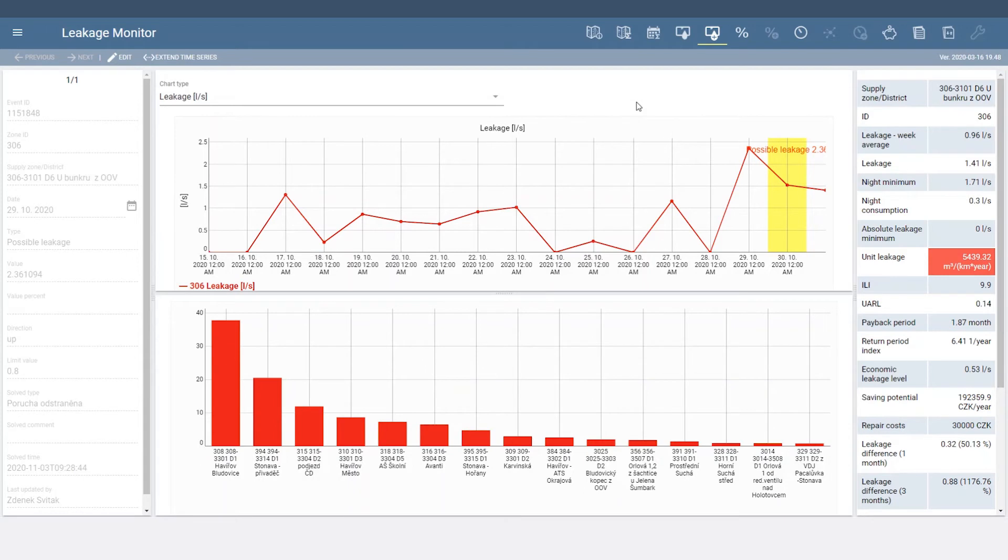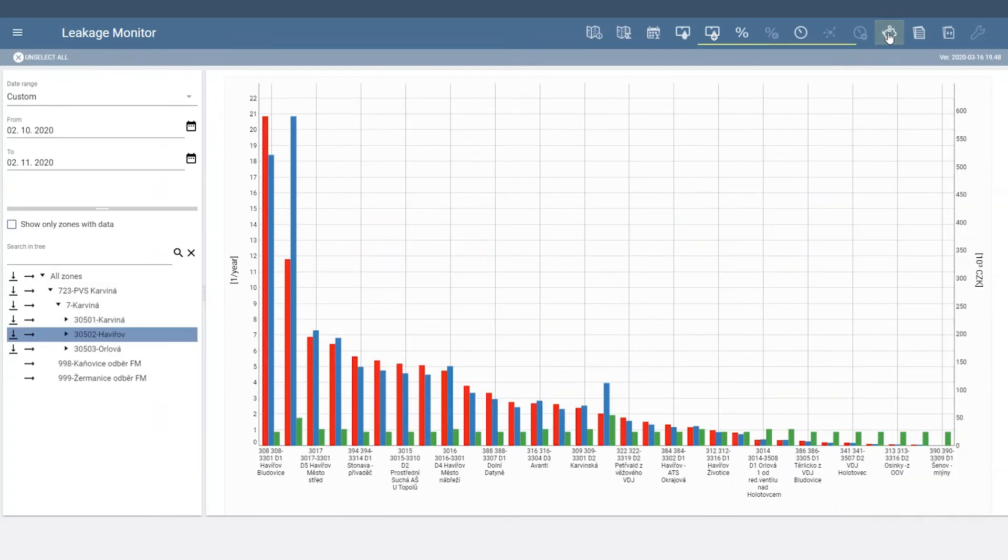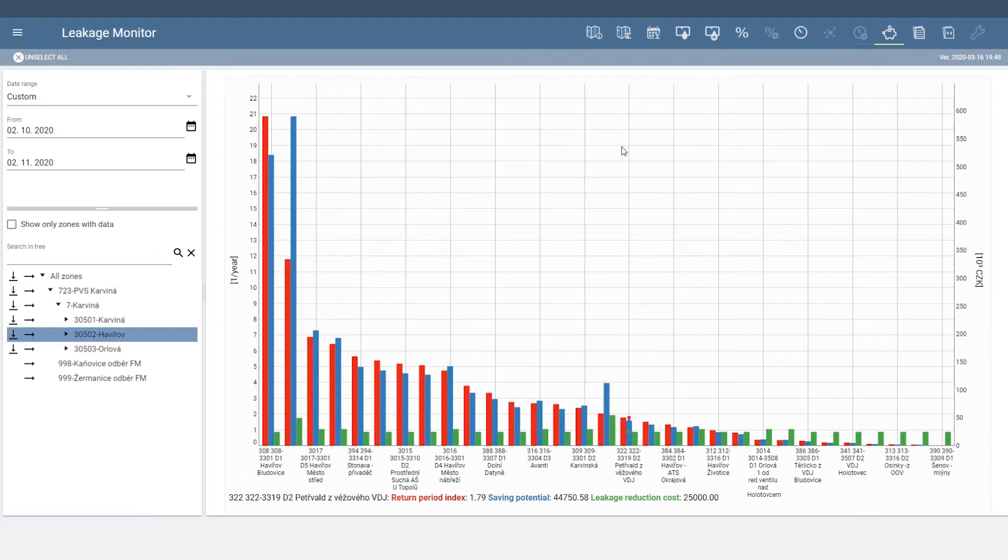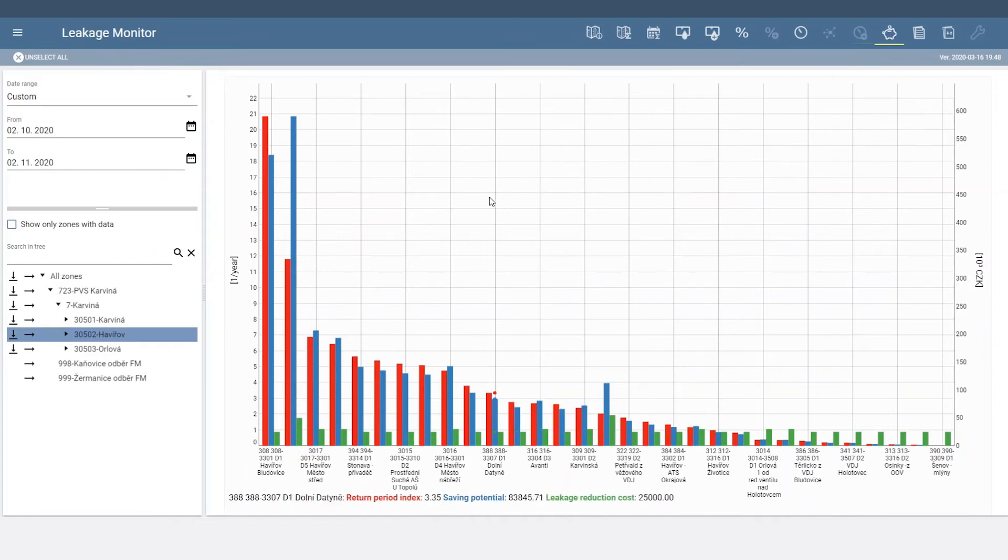The economical priority of DMAs is shown in the Economy tab. Leakage Monitor automatically compares the cost of leakage reduction with the marginal cost of water, which can be saved in each DMA, and calculates economical level of leakage, payback period, and payback period index.